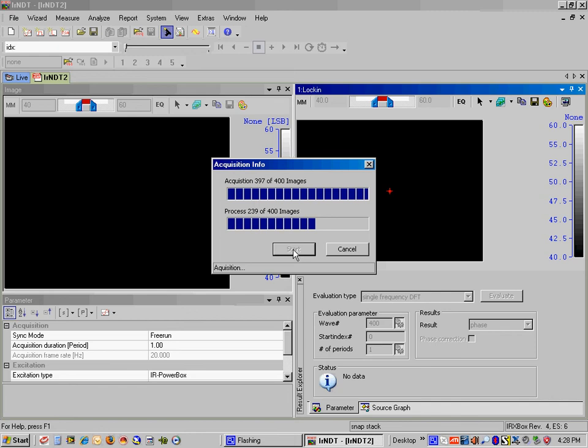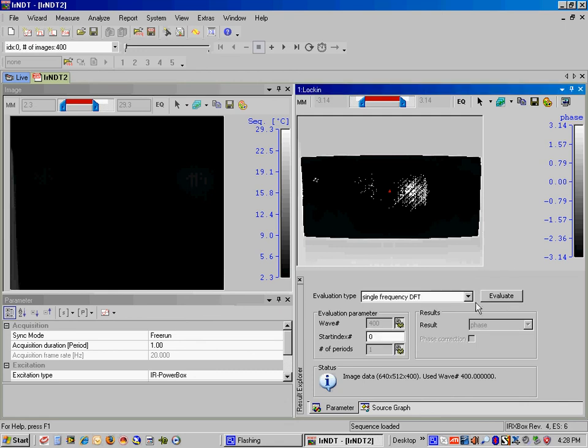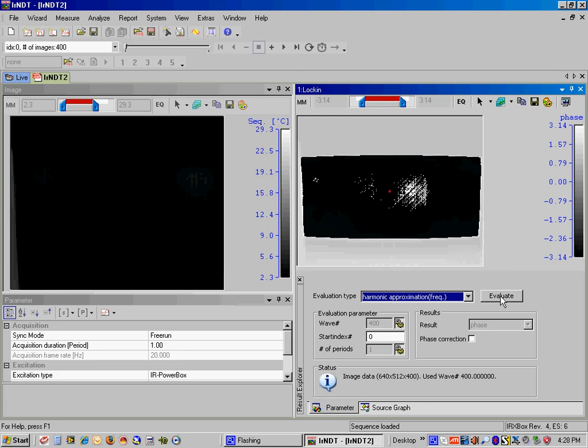All right. So we've got our first resulting image here. What we want to do is reset the evaluation type so that we can go to Harmonic Approximation and then re-evaluate. That should give us a much clearer image of the flaws behind the composite panel.